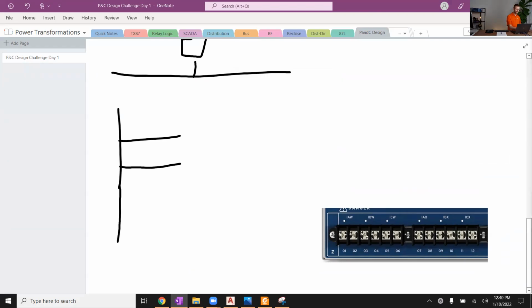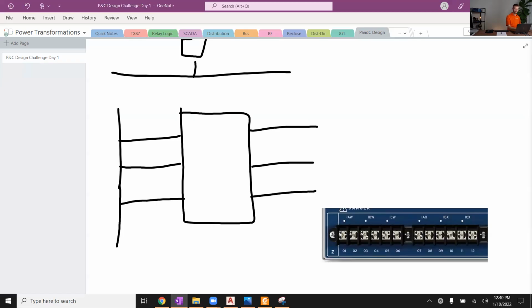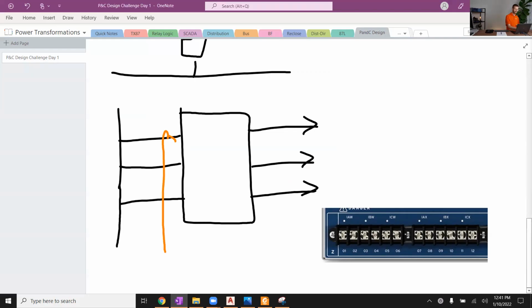Let's do 3 phases this time, okay? A, B, and C. And let's do our circuit breaker a little larger this time. And A, B, and C coming out of the breaker. In a circuit breaker, we typically have 6 bushings, 1, 3, 5, and 2, 4, 6. I'll draw that up in a little more detail in a little while. But let's draw our CT here. This is on the A phase. We're going to come into the A phase polarity dot. Let's note that the primary polarity dot, secondary polarity dot. So what happens is you wire the secondary polarity dot of your CT to the polarity dot on the back of your relay.